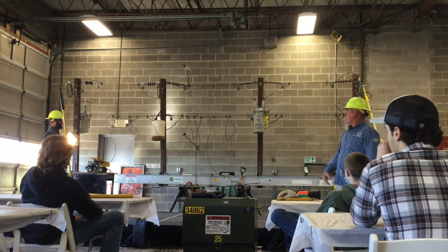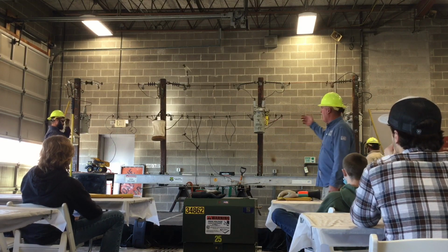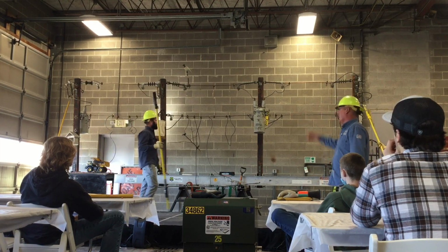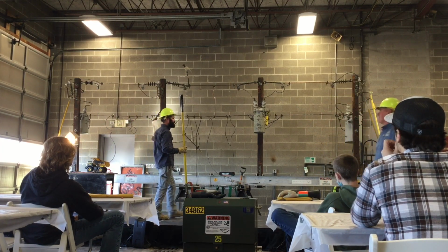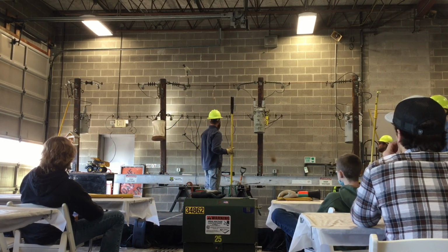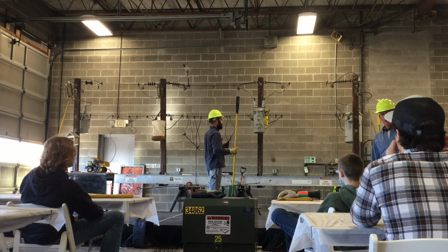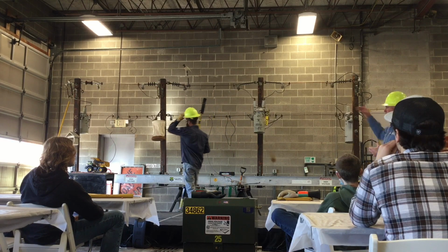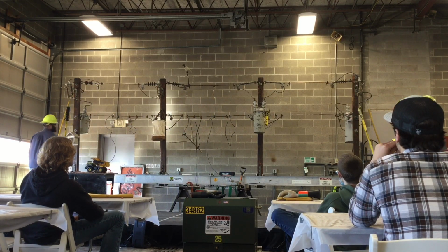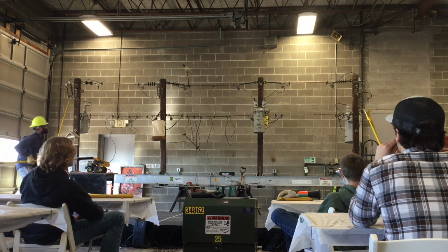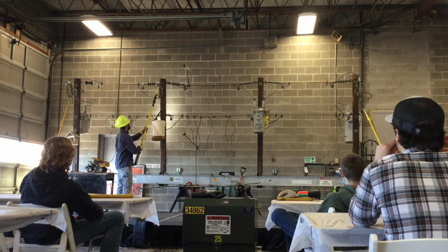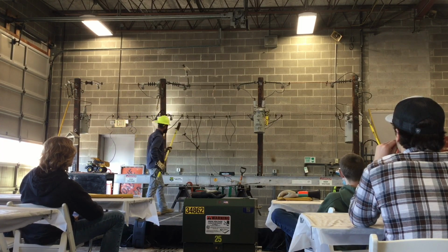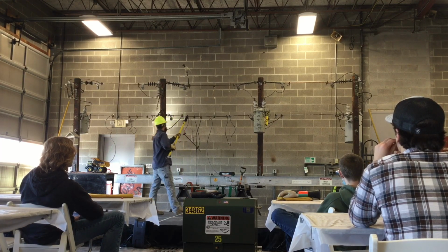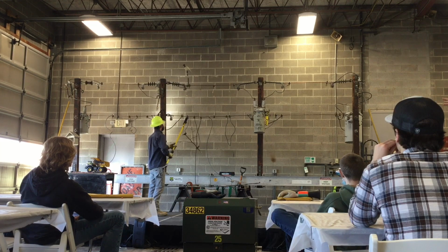Like I said, that's a difference of potential. That pole is sitting there operating at 0 volts, everything's tied to ground. The bird's at 7,200, reaches over the insulator - we get this a lot. We have birds, squirrels, you name it, get on top of transformers, on top of cutouts, and they're fine when they're energized, but then they go to jump on the pole or on this transformer. We have the primary bushing - can you see this red tape on the top bushing? That's our primary bushing. Sometimes in the wintertime these transformers get warm. The case, the actual transformer, is all grounded, so it's sitting there at 0 volts. You've got 7,200 volts on the primary, and squirrels get up there standing on the case, reach up and grab that primary bushing, and boom - difference of potential. See it.